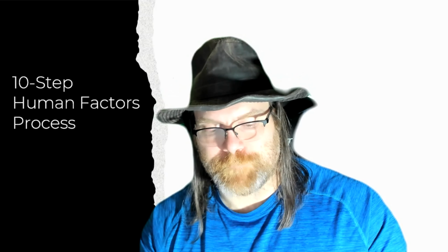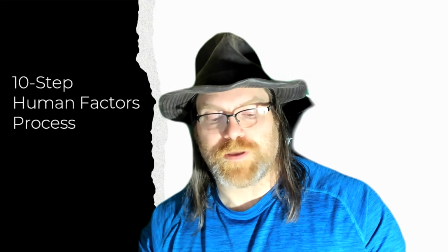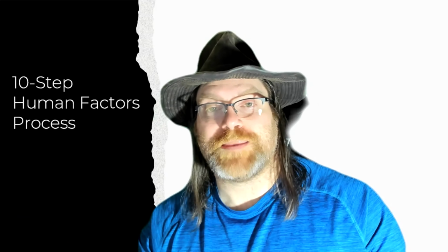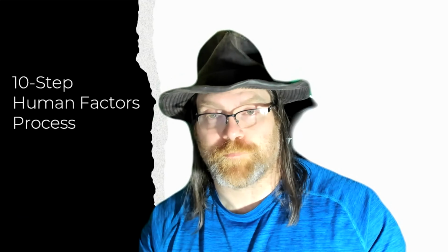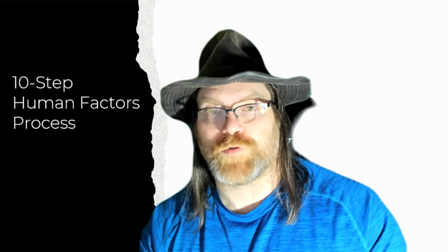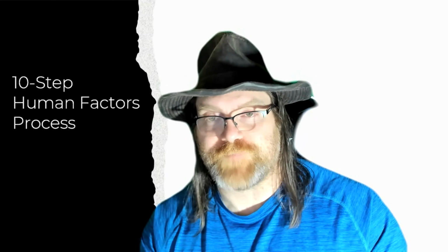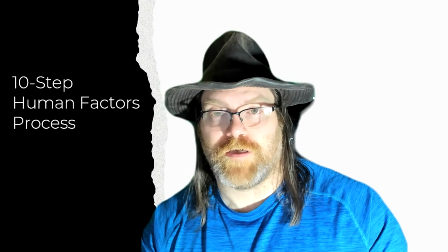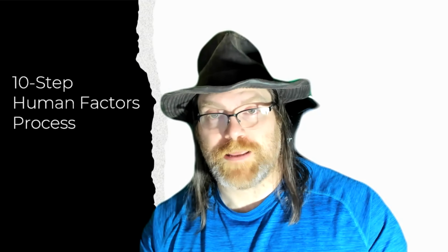You want to make sure that the formative testing is evaluating different design options. That's one use. Another use would be to identify any unforeseen use errors that you hadn't even thought of during your brainstorming sessions, or uncovered when you were doing, let's say, a state-of-the-art review or a review of adverse event databases. You can use your formative testing to develop instructions for use, or an IFU. You can use it to develop training materials.